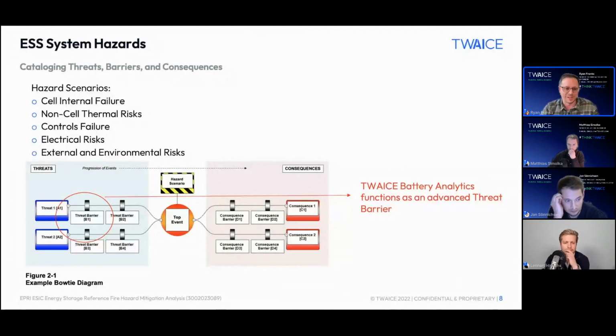This is called a bow tie diagram. On the left, you can see threats and threat barriers that all lead to a hazard scenario, and then there are consequence barriers and consequences. A simple example going from left to right might be an internal cell failure of some type, perhaps a cell manufacturing error. A threat barrier would be something like a disconnect switch that might isolate that. The hazard, if that doesn't occur, would be something like a fire, put simply. A consequence barrier would be something like a fire suppression system, and a consequence would be a fire.